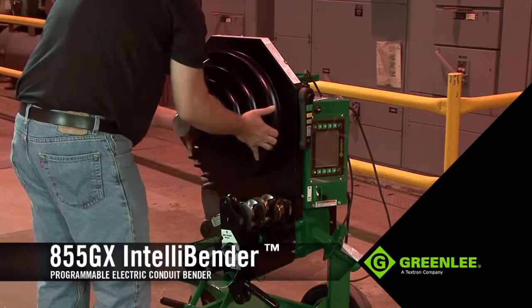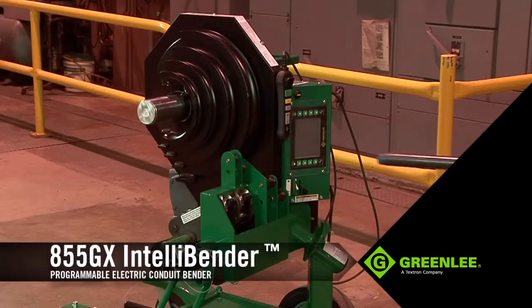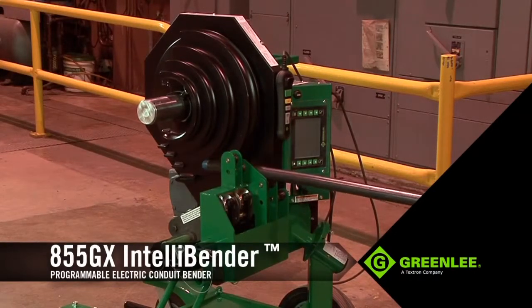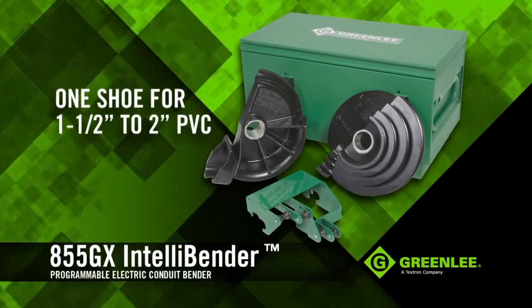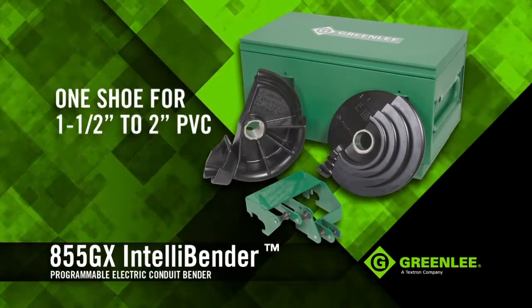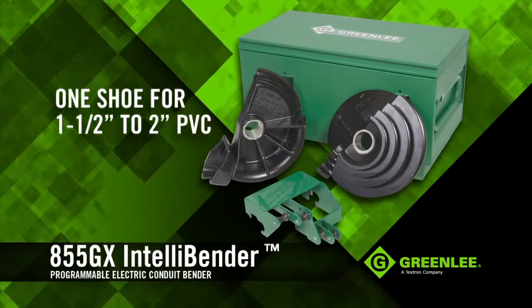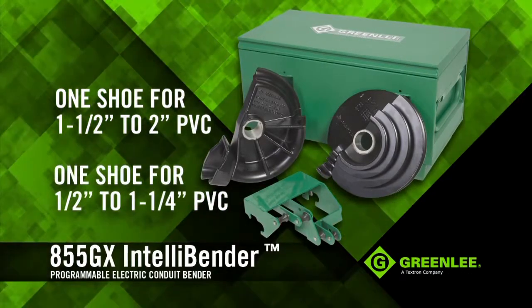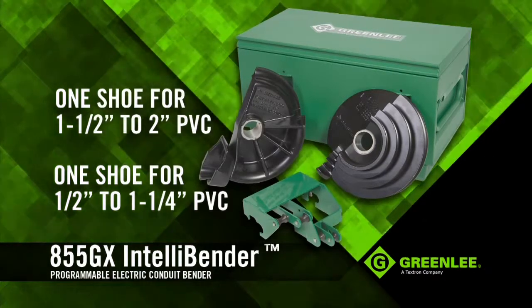However, for bending PVC-coated rigid conduit, Greenlee offers a convenient 2-piece shoe group that accommodates ½-inch to 2-inch diameters. One shoe, designed to bend 1-1/2-inch to 2-inch PVC, lines up directly with the support rollers built into the unit. The other shoe will bend ½-inch to 1-1/4-inch PVC and uses an additional support roller that clips directly onto the bender.